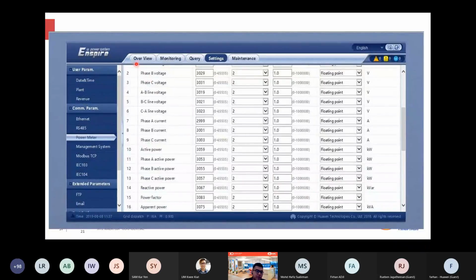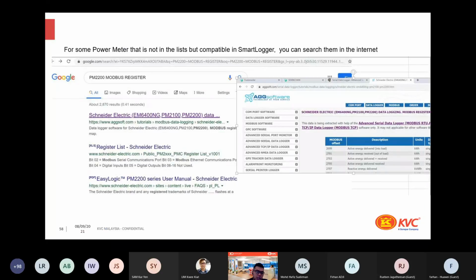You can see there are different parameters you want to capture. Always fill in the correct address according to the Modbus register list of the power meter. You can search the Modbus register list online, download it, and cross-refer on how to fill up the register list within the Enspire web portal.